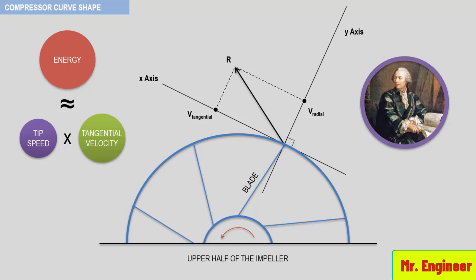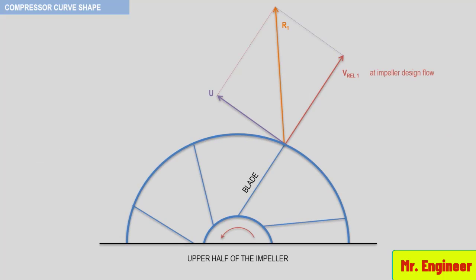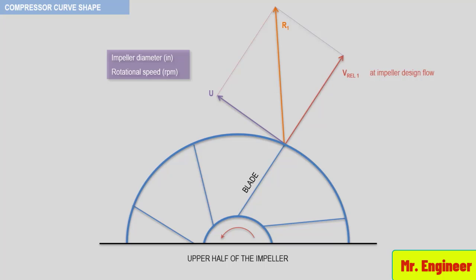Let's now assume that the head required by the process changes such that the flow through the impeller reduces. Examining the discharge velocity at this reduced flow condition: assuming rotor speed is constant, the tip speed value does not change, since tip speed is a function of impeller diameter and shaft speed. However, the velocity relative to the blades will be reduced as a result of a lower volume flow passing through a fixed area, resulting in a lower velocity relative to the blade at the discharge.